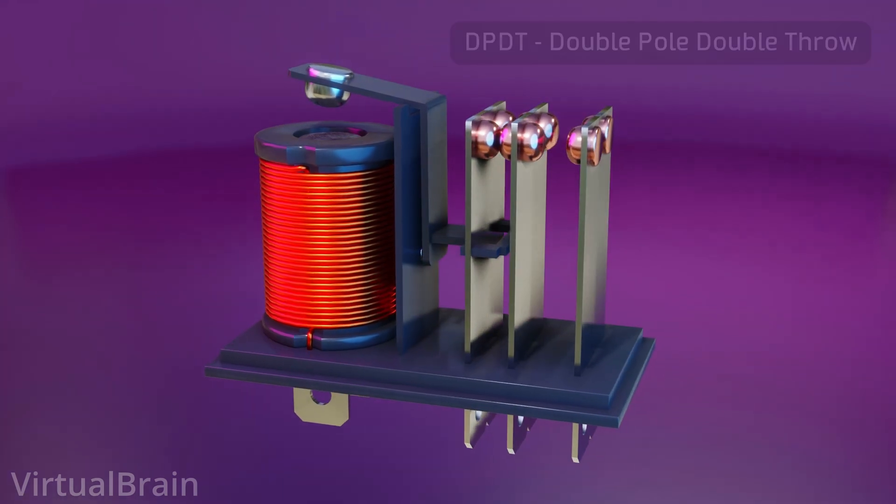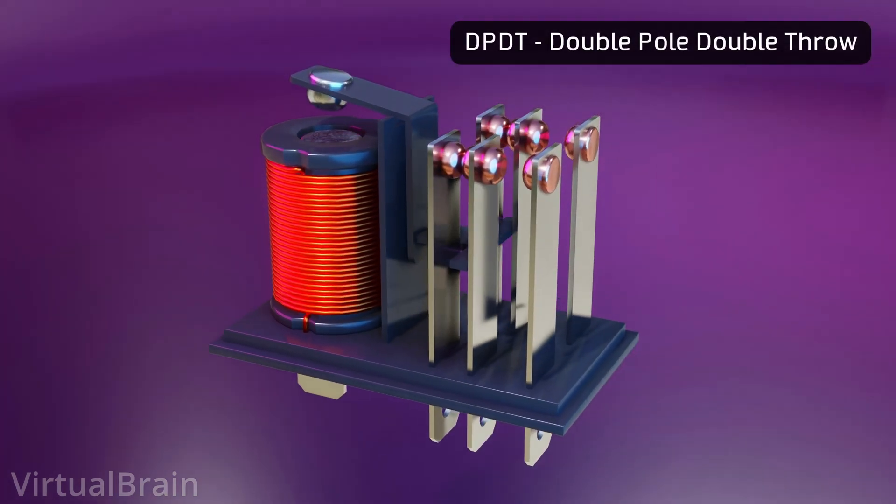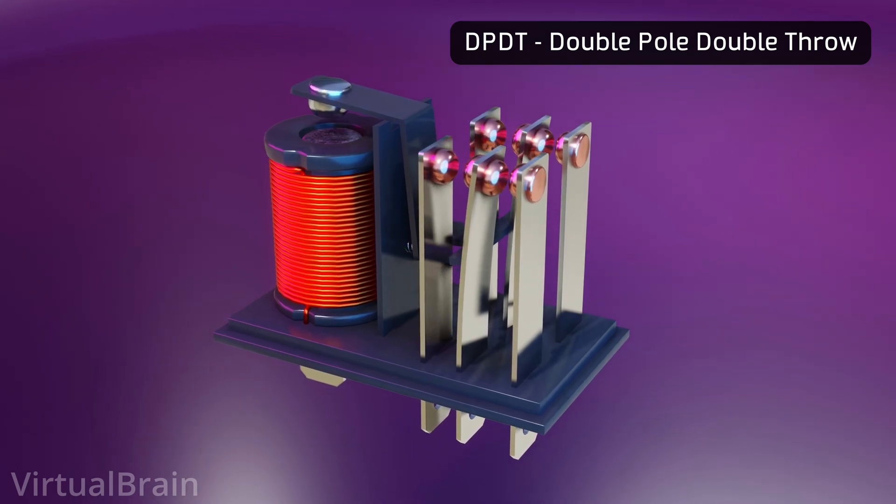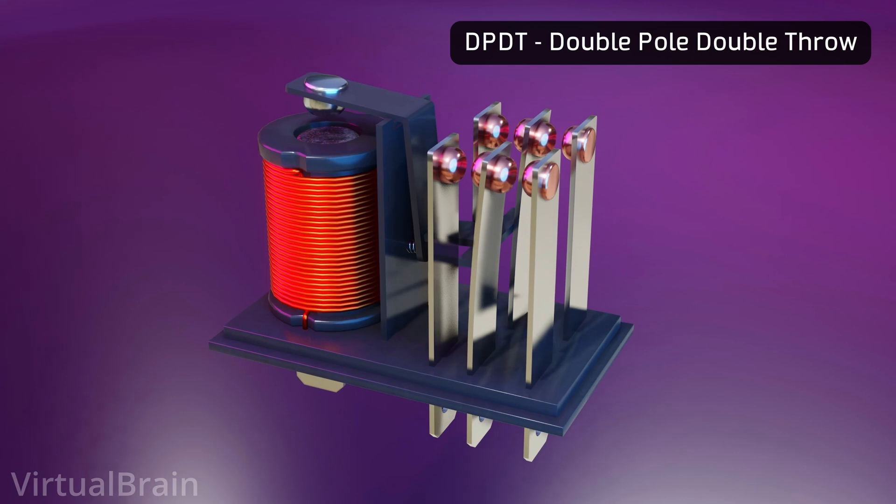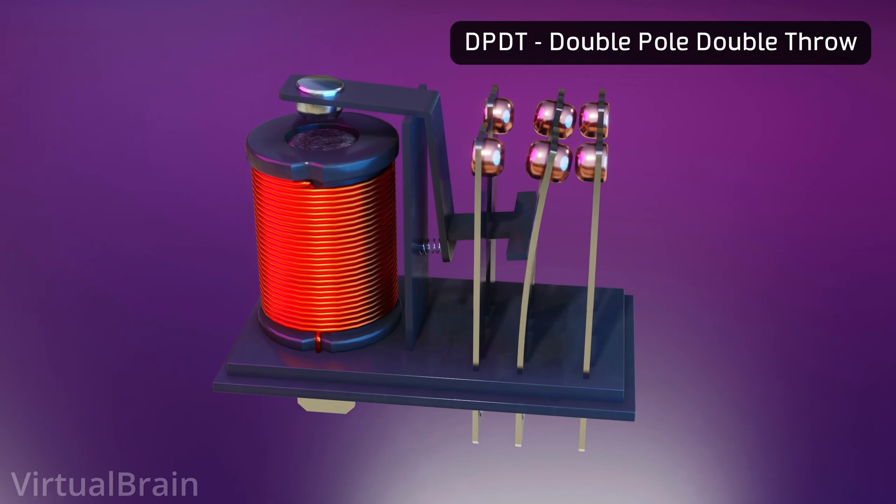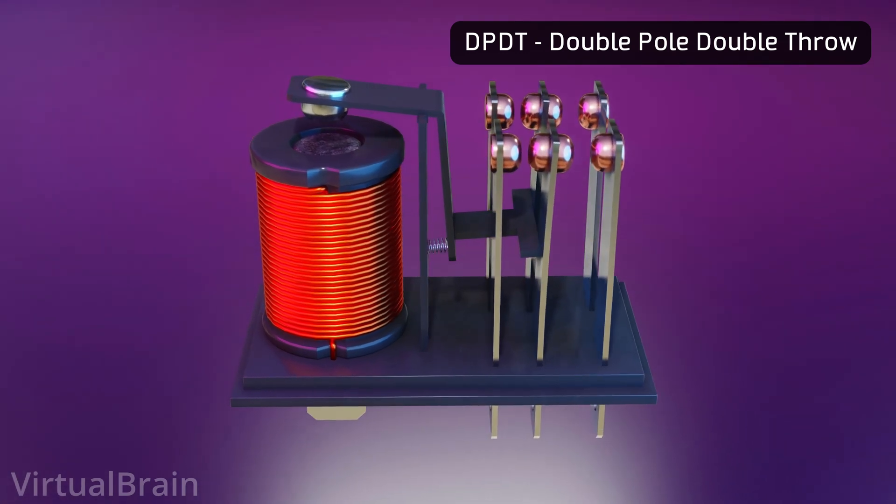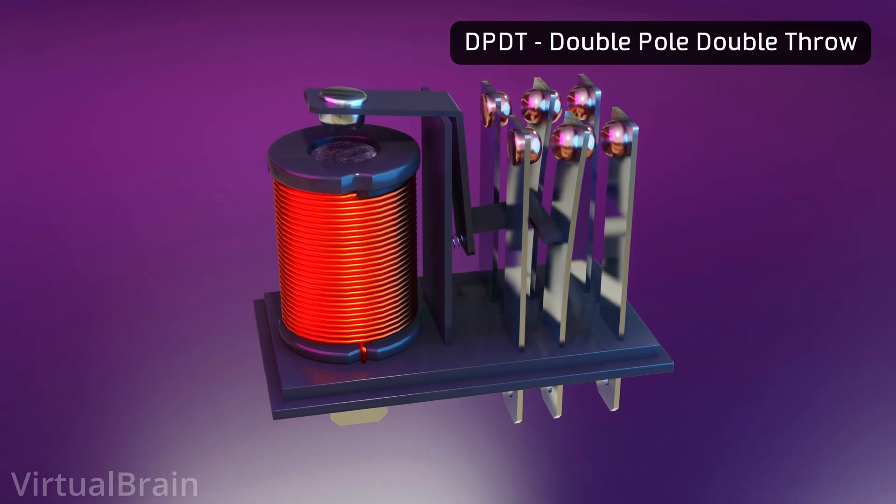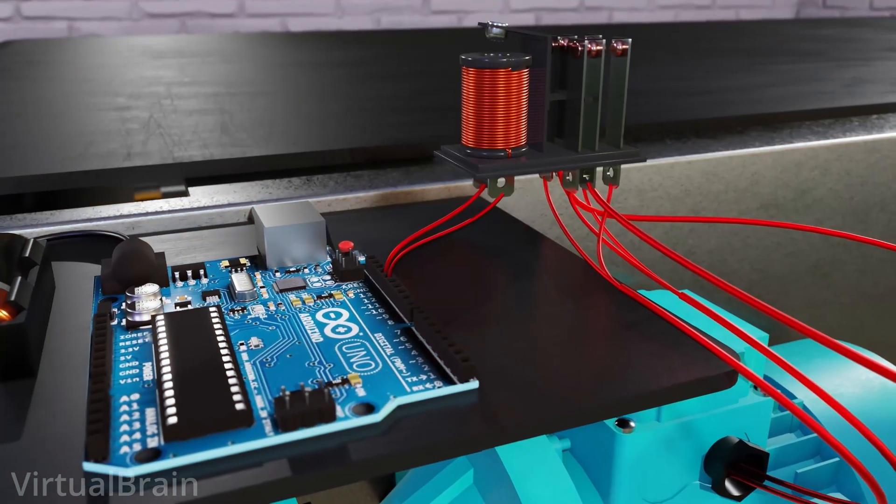On the other hand, if we switch from a single pole relay to a double pole relay, it would be equivalent to having two equal relays being activated simultaneously by the same input signal on the electromagnet, resulting in something like this. In this case it would be a double pole double throw relay. Here the possible applications might not be so obvious, but an example would be to allow changing the direction of rotation of the motor.